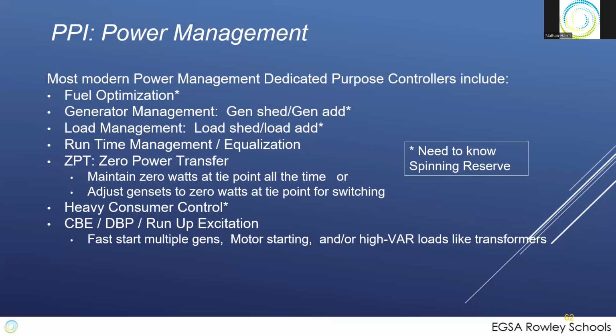And then ZPT, zero power transfer, is minimizing system disturbance or wear and tear on switchgear and equipment by driving the generators down to a very low power point and then opening the breaker. So that's one definition: when it comes time to take a generator offline, you reduce its fuel until watts get down to some low level and then open the breaker. So zero power transfer. At zero power, we transfer, we open the load. Or as you're coming on, you bring a generator on the bus, in sync, so very little current flows until you start to increase the fuel. Then current takes over and you back off the other one. So you're transferring power from one to the other at a low kW level to save wear and tear on the system.